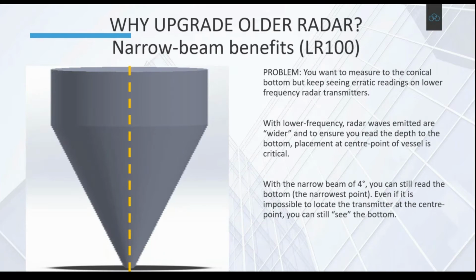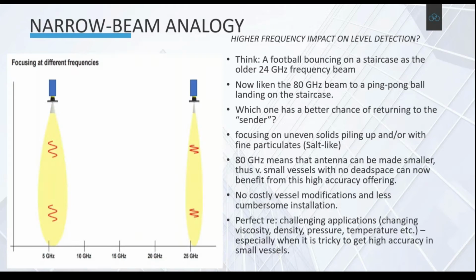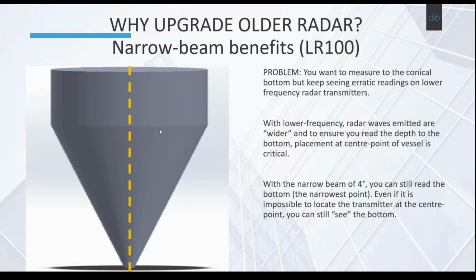So why the narrow beam? As you saw here, it becomes narrower as the operating frequency increases. Narrow beam is obviously - if you thought the large wide beam of the 5 or 26, then the beam would probably hit here, the sides, and in a tall silo, could be 15, 20, 30 meters, say you're trying to read the bottom, and with the narrow beam you will be reading right through down to the bottom.